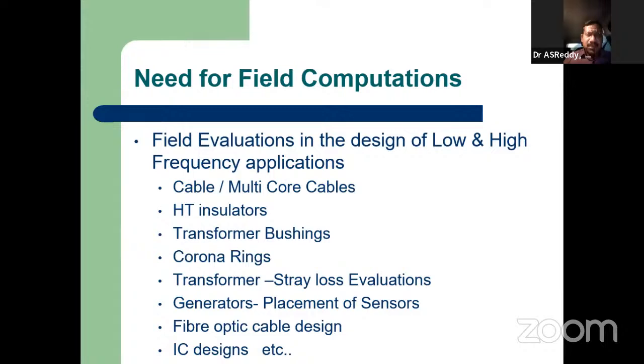And even in transformer bushings, in designing them, the shape and placement of the conductor and the corona rings matters a lot. For example, when designing an insulator, bushing, or a string of insulators, to distribute the field in a uniform and safer way, we design corona rings. The decision of placement, shape, and type of corona ring also needs this kind of field computation.